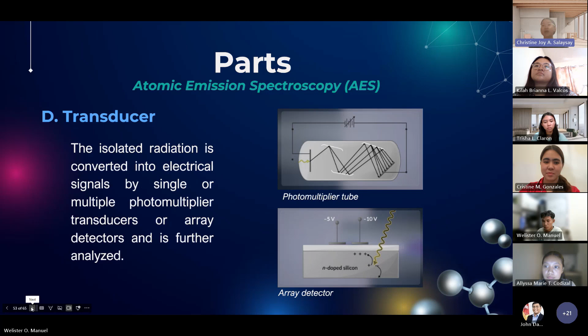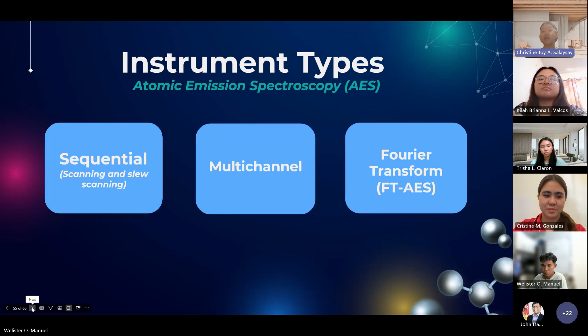So for the instrument types, there are various instruments that are used to analyze the emitted light. First, the sequential spectrometers. These measure one element at a time by scanning different wavelengths sequentially. Multi-channel, this specifically refers to instruments with multiple detectors assigned to different wavelengths, enabling simultaneous detection. Next, the FTAES. This is a high-resolution technique that utilizes Fourier transform methods to enhance signal detection and spectral resolution. This provides greater sensitivity and precision, particularly for trace element analysis.